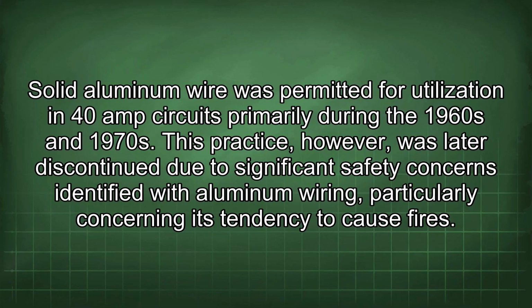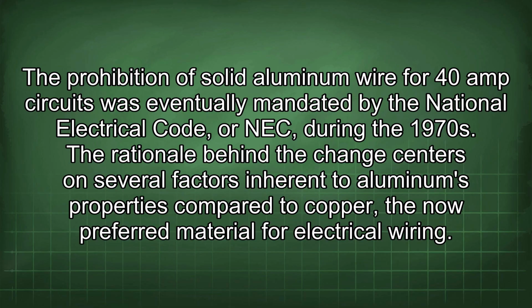Solid aluminum wire was permitted for utilization in 40-amp circuits primarily during the 1960s and 1970s. This practice, however, was later discontinued due to significant safety concerns identified with aluminum wiring, particularly concerning its tendency to cause fires. The prohibition of solid aluminum wire for 40-amp circuits was eventually mandated by the National Electrical Code, or NEC, during the 1970s. The rationale behind the change centers on several factors inherent to aluminum's properties compared to copper, the now preferred material for electrical wiring.